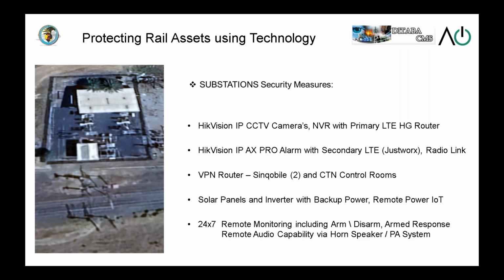We've got 24/7 remote monitoring. When any engineer or technician needs to visit a substation, that comes down to people, technology, and process. Before a staff member visits, they call the control room. We can see them live on the display, and the alarms are disabled remotely. They go in and do whatever maintenance they need to, and we arm the alarms and systems again when they leave.